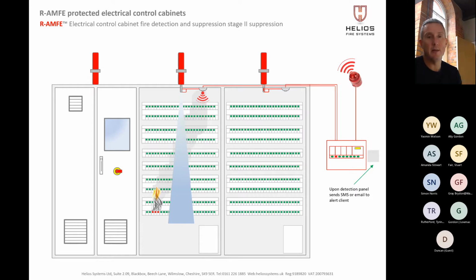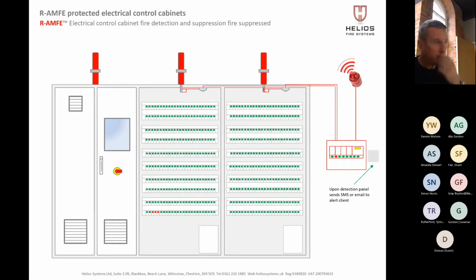So once we have the signal for deluge, the bulb shatters, the contents come out of the cylinder. The liquid at 40 degrees then becomes a gas. It's a non-toxic gas. There's no issues. It's not like FM200 or any other gas that would mean operatives need to leave the building or get away from the vapor. You can sit by it, you can breathe it. It's not toxic in any way. So once the system's actually done its job, the fire's out, so we can see the bulb's gone. Yes, we've got some damaged components down here, but you've protected the system from fire spread.